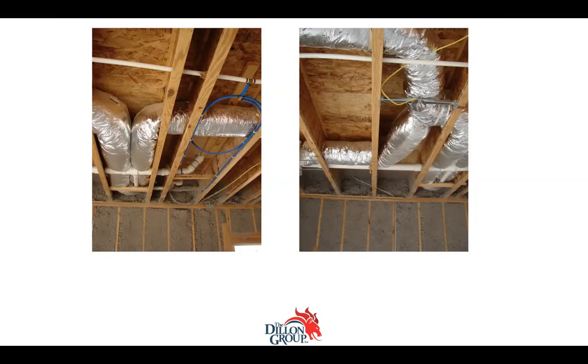And what do you get? One duct of equal size coming off of that. So now you've got a certain volume of air moving through, let's say a 10-inch diameter duct, and then all of a sudden, you still have a 10-inch diameter duct with that volume of air moving through it, but now it's two 10-inch diameter ducts. Well, the volume of air moving through that is going to be a lot less. The velocity is going to be a lot lower, and you're not going to get very much air coming out at the end.